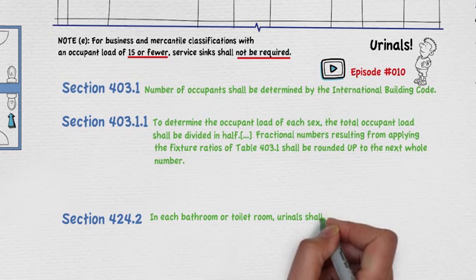You see how this is beneficial? The number of water closets did not change — we still need 3. The number of drinking fountains did not change either — we only need 2. However, we did add enough to require one more lavatory and one more service sink. As an FYI, in most jurisdictions, even though we are noted to require 2 service sinks, it is often allowed to reduce to 1 if it's the same tenant. The plumbing code is not very clear and could be debated, so a plan checker could potentially ask for 2. Please provide a comment so we can all benefit from how other jurisdictions apply this.